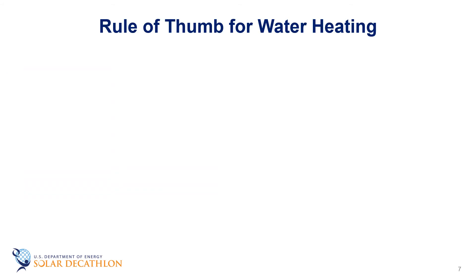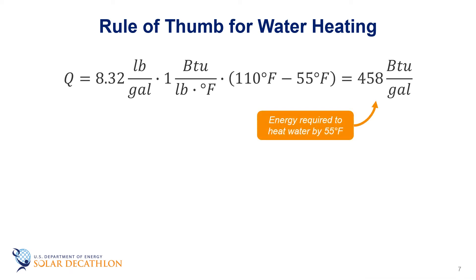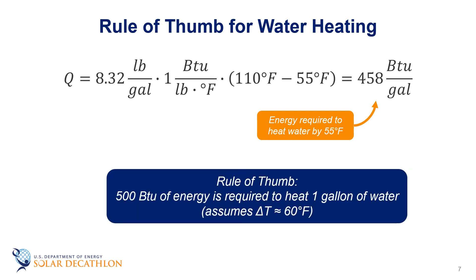Another metric that is sometimes used is the amount of energy to heat a gallon of water for the needed temperature difference. In this case, 8.32, the density, times the change in temperature, 110 minus 55 degrees Fahrenheit, is 458 BTUs per gallon of water heated for that 55 degree temperature difference. A rule of thumb typically talks about 500 BTUs per gallon, so a little bit higher than the number we just calculated. This 500 BTUs per gallon is a handy number as a quick tool to think about how much energy is needed for hot water, remembering that it assumes a certain water supply temperature as well as a temperature of the hot water.